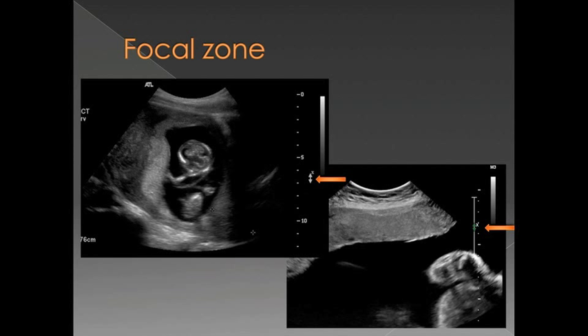So the focus or focal zone, if you think back to our beam diagram that we showed before, I told you that the focus depth is set electronically. And this is done differently in different machines. This is actually two different machines here. The first machine here on the left gives you a small fixed focal zone that has a range of about a centimeter. And you can add and subtract numerous focal zones on this machine.